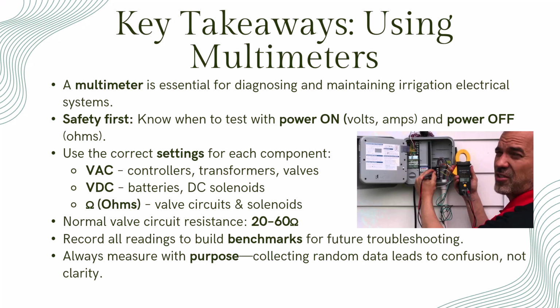Let's wrap up with the big picture. A multimeter is one of the most powerful tools in irrigation maintenance, but it's only effective when used with purpose, precision, and safety. Always know what you're measuring and why. Use volts to verify power, ohms to check resistance, and amps only when you're trained and equipped for advanced diagnostics. Remember, power on for volts and amps, power off for ohms, and a healthy valve circuit usually reads between 20 and 60 ohms. Finally, record your measurements. Over time, these readings become your benchmark library, the data that separates guessing from skilled troubleshooting.